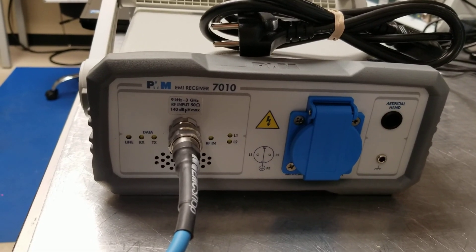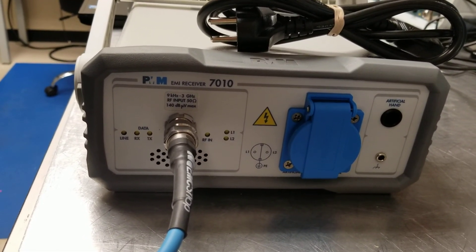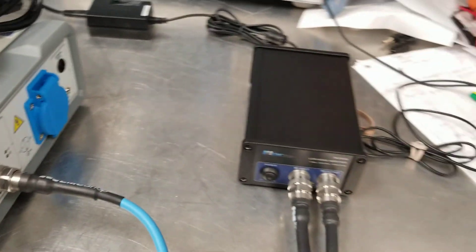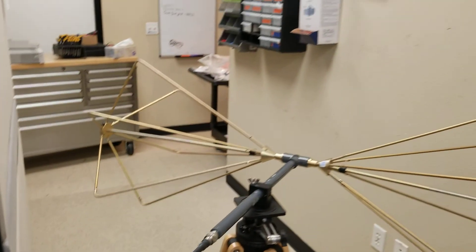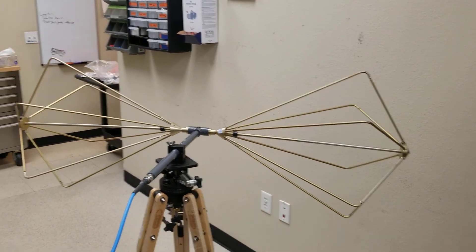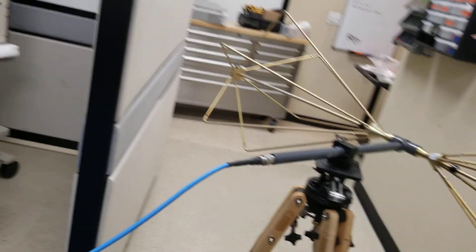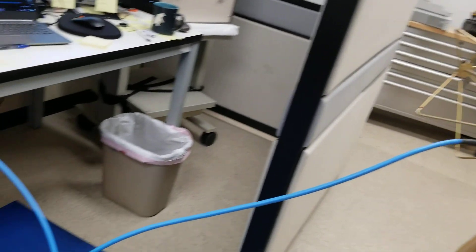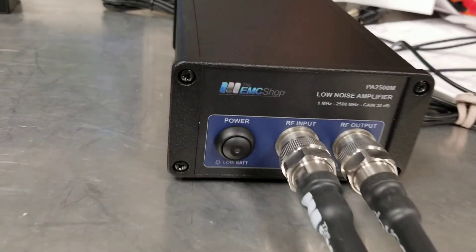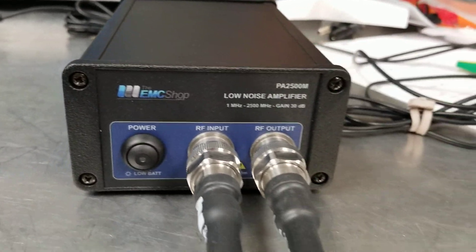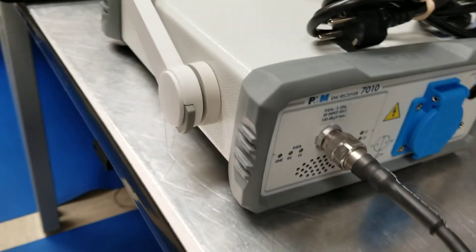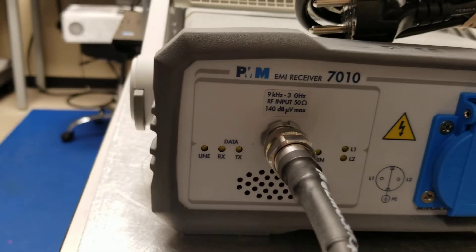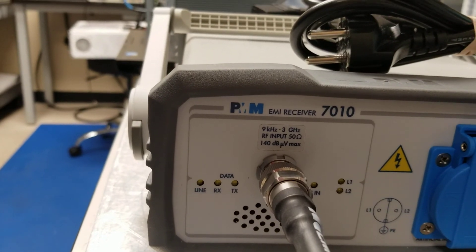This video shows how to connect the PMM 7010 using a preamp attached to a biconical antenna. You would bring the output of the antenna into the input of the preamp and take the output of the preamp connected up to the RF input of the PMM 7010.